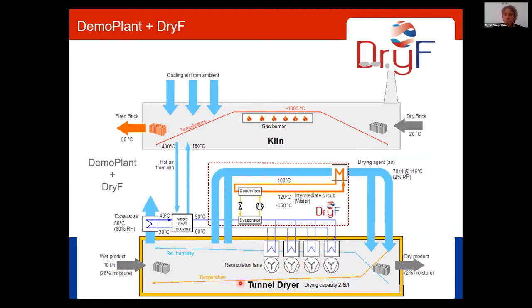But since this dryer building is limited in space, it's a decades old building, and it's not possible to reach the residual moisture needed to be ready for the kiln, we need a higher temperature. And this is where DryF comes into this project. DryF picks a quite small part of the energy of the 90 degrees water circuit and lifts and provides temperatures of up to 160 degrees.